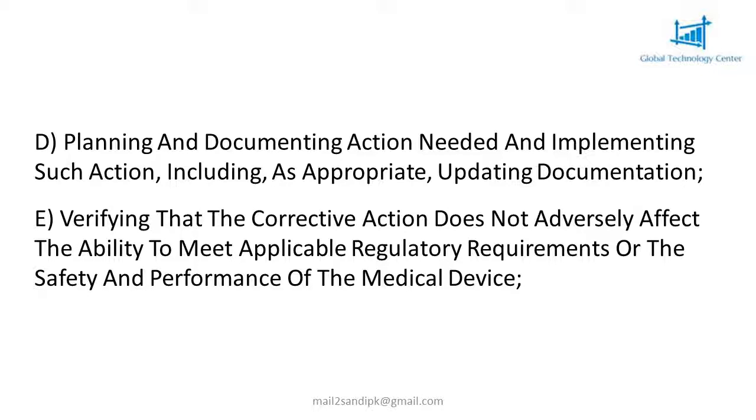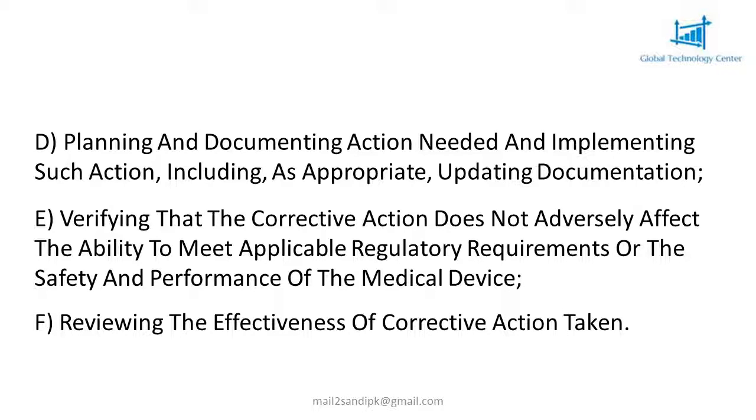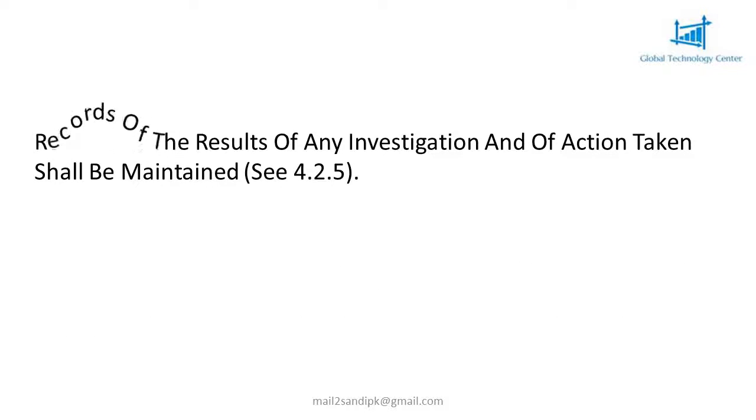E. Verifying that the corrective action does not adversely affect the ability to meet applicable regulatory requirements or the safety and performance of the medical device. F. Reviewing the effectiveness of corrective action taken. Records of the results of any investigation and of action taken shall be maintained.